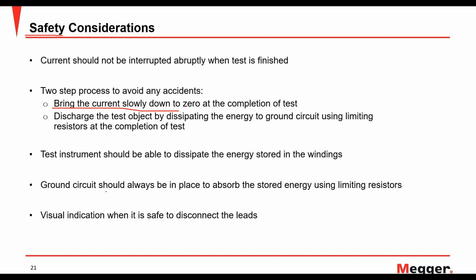And the ground circuit should always be in place to absorb the stored energy using limiting resistors. So always make sure you have good grounding connections. Once the test is done, it is all going to ground. And the instrument itself will give you a safety indication that it has discharged all the energy that it supplied to the winding. It's going to discharge, and then it's going to tell you it's now safe to disconnect the leads. So that's when you disconnect the leads.